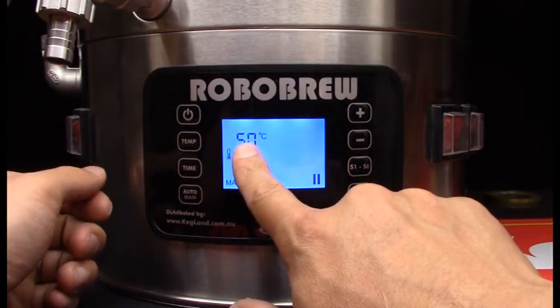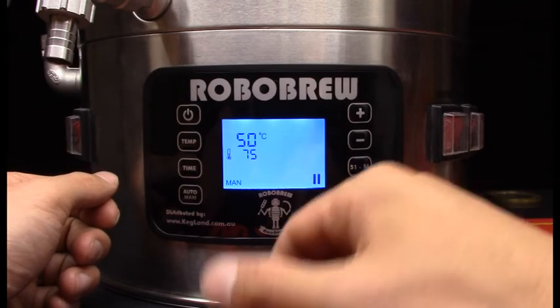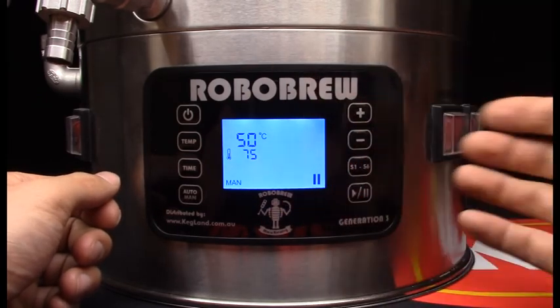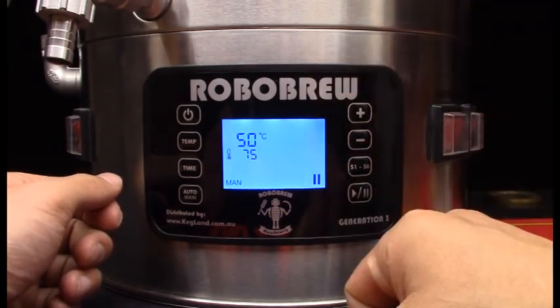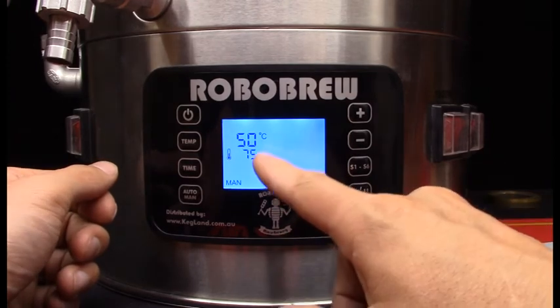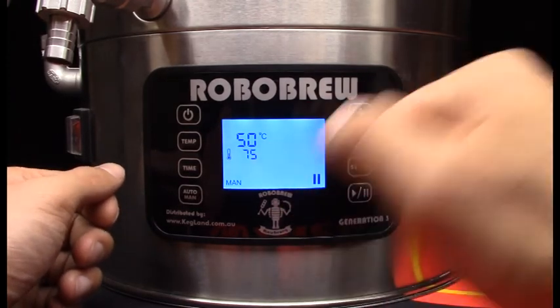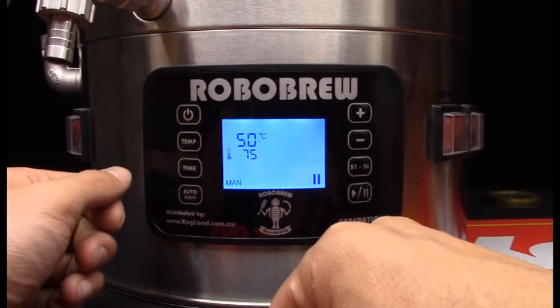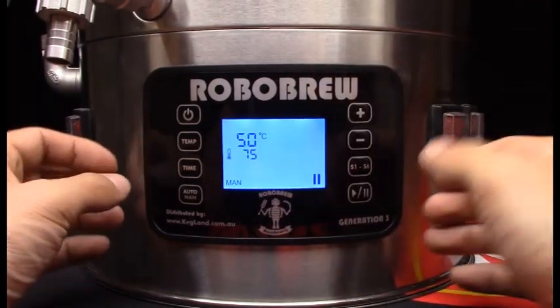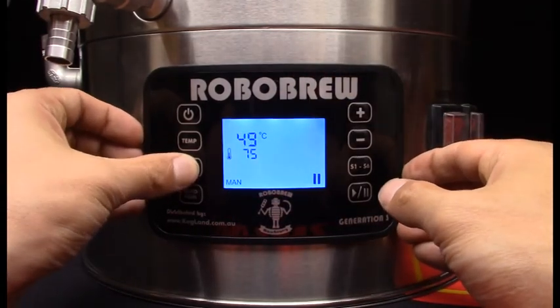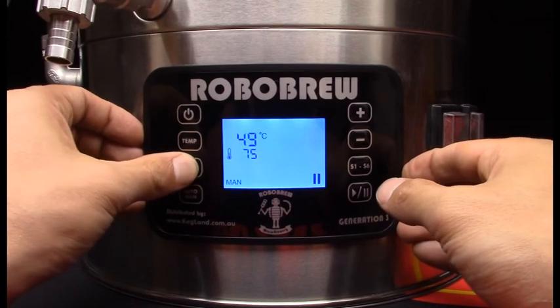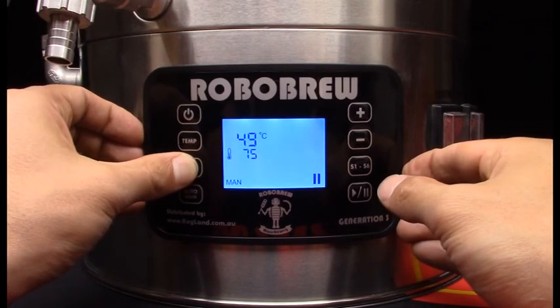So let's say for instance I'm reading 50 degrees on the display here but actually I've checked the temperature and actually it should be 55 degrees let's say. So I know that my displayed temperature needs to increase by five degrees. All you need to do is you can go into auto or manual mode it doesn't really matter but then click on the time button and then hold it down and you can see...